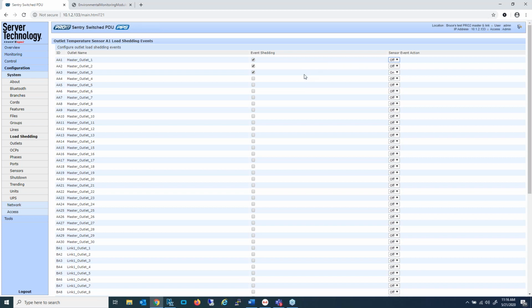The purpose for switching on would be, for example, if you have cabinet doors with built-in fans or fans in the top of the cabinet, you can have those plugged into the PDU and they don't need to run constantly. If temperature exceeds your chosen threshold, we can automatically switch the outlet on to turn on those additional fans rather than turning devices off.